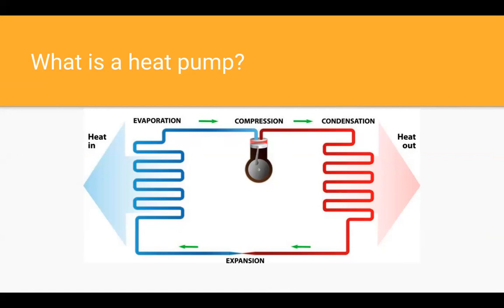This is a diagram of a refrigeration cycle. Basically you have a hot side and a cold side. The evaporator absorbs heat from the air by way of the evaporation of the liquid refrigerant turning into a gas. As that liquid evaporates in the evaporator, it absorbs heat from the air, and then that gaseous refrigerant gets sucked into the compressor. The compressor squeezes that gas, which increases its temperature — that's a very key part of it. Everyone says, how can you make heat from 10-degree air? Well, that's how: you absorb the energy through evaporation, and you raise the temperature by compression. Then the hot gas goes into the indoor unit in the house, where it's circulated through a heat exchanger. A fan moves the air across that heat exchanger, cooling the hot gas to a liquid, where it goes back out to the evaporator, evaporates into a gas, gets squeezed, increases in temperature, blows off in the condenser inside, and it's just a continuous cycle there.